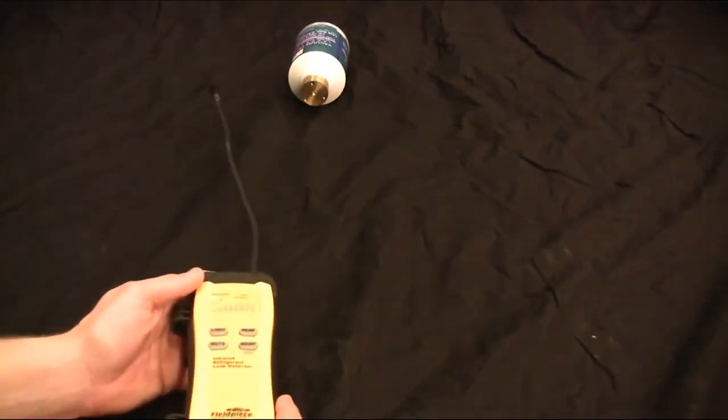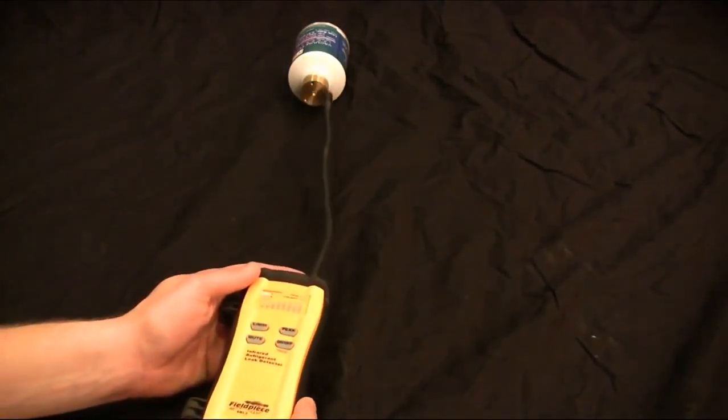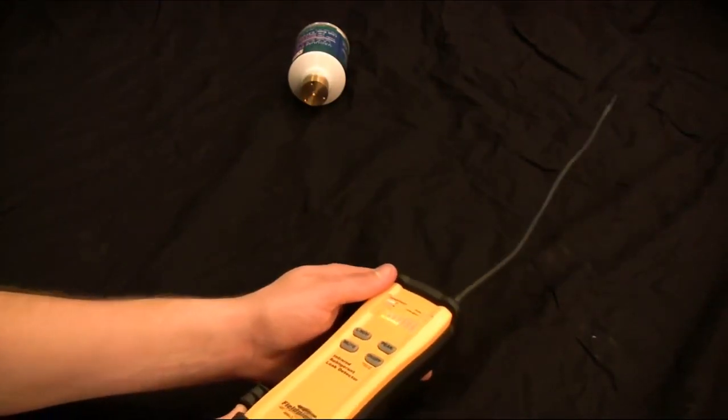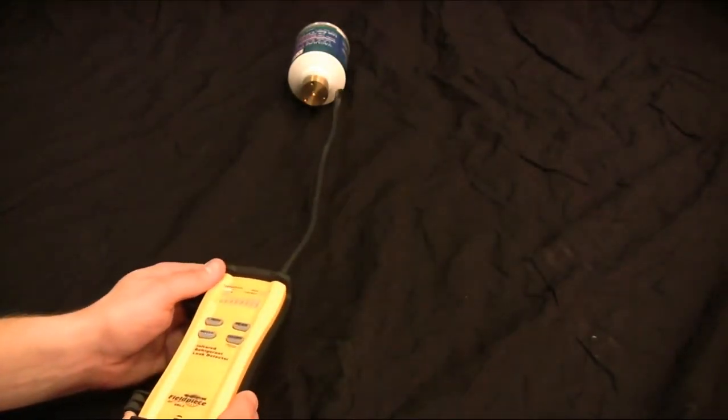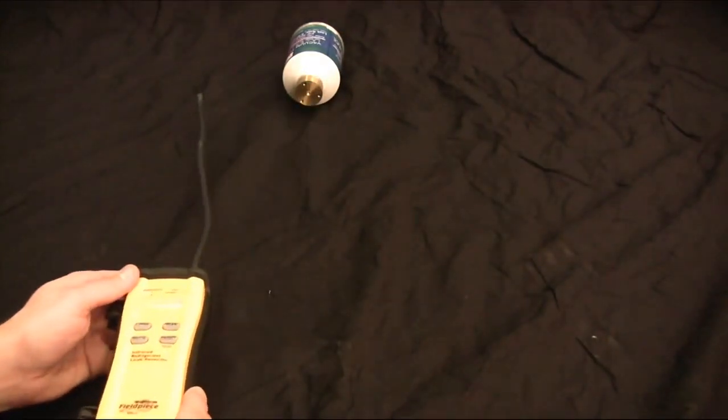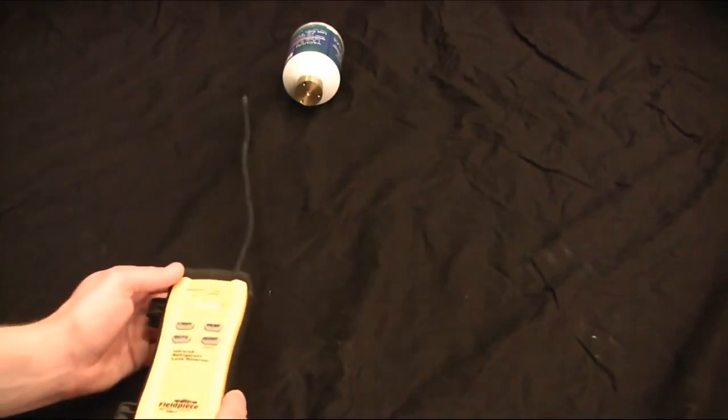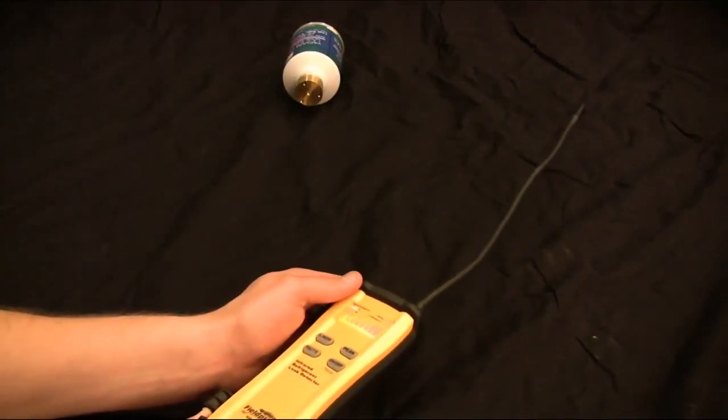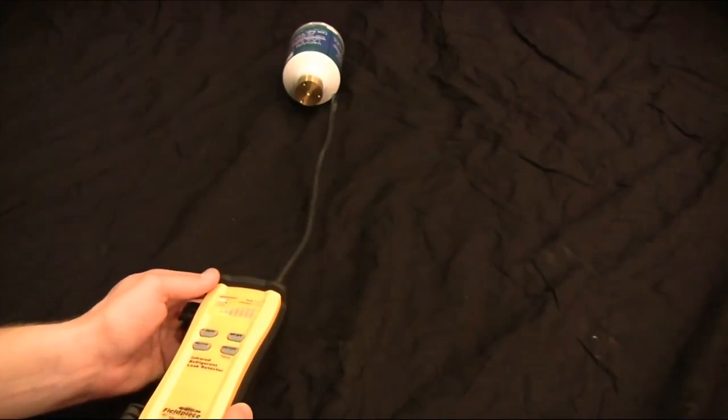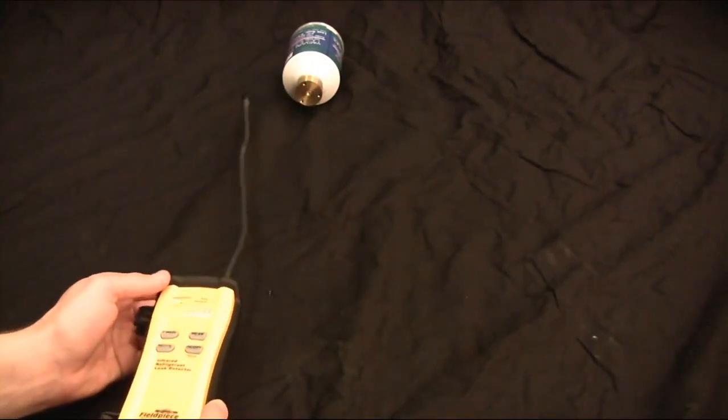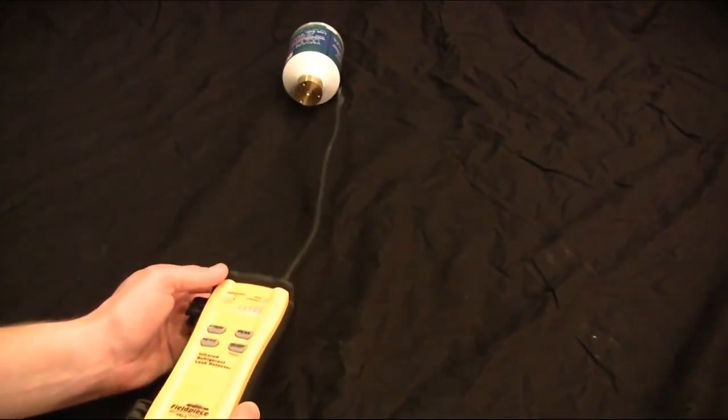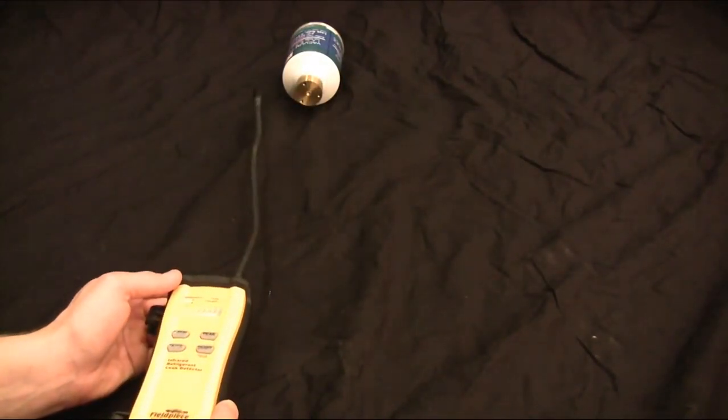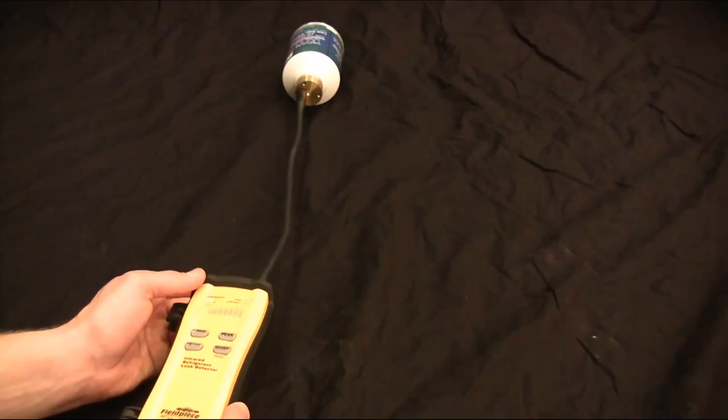Let's show you how it works in action. What you want to do is just slowly move it across the leak and sweep it by. And you'll see that it goes off. Now as it goes off, you want to pass it and keep moving and then sweep back. And it will go off again as you keep on passing the leak. And so this is what we call the sweeping method. You just want to dial it in until that buzzer stops going off.